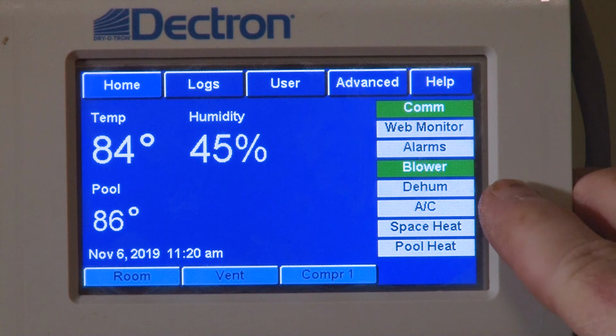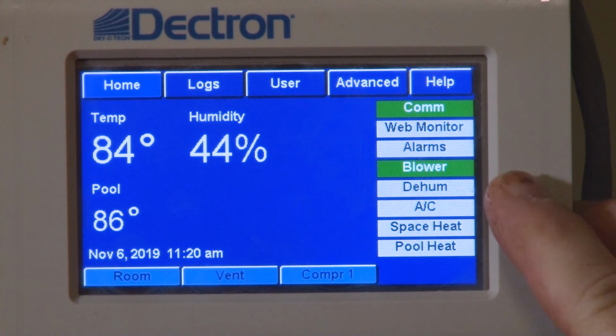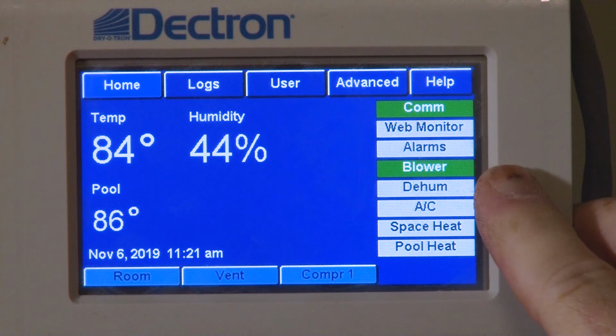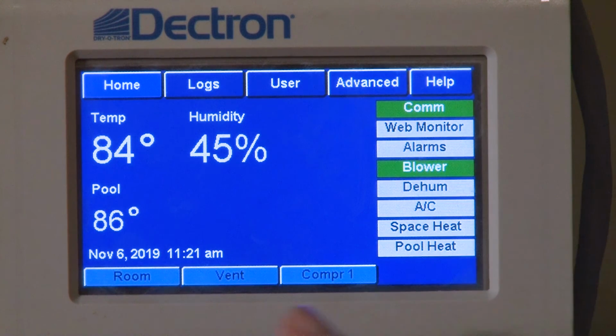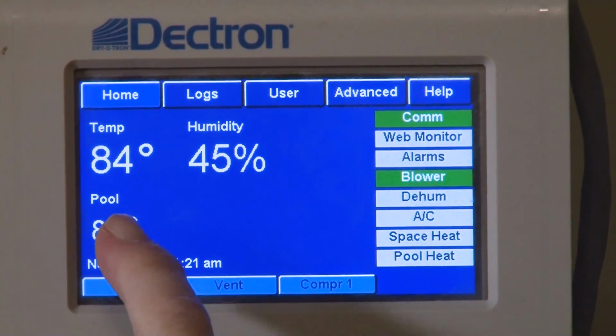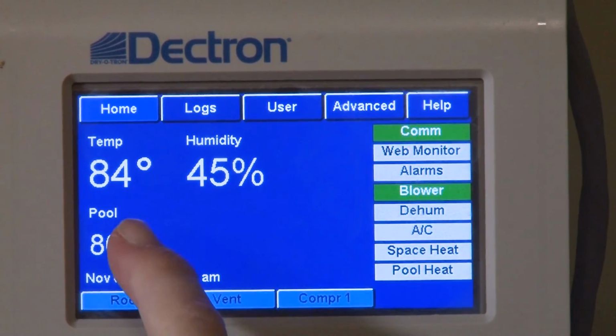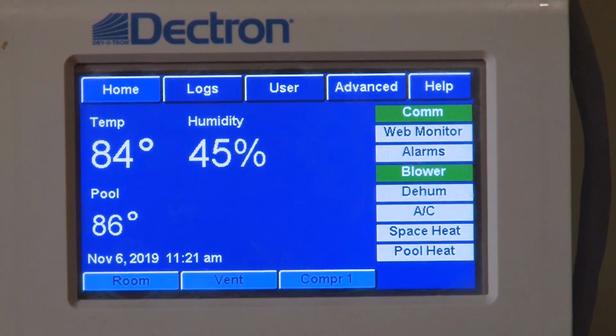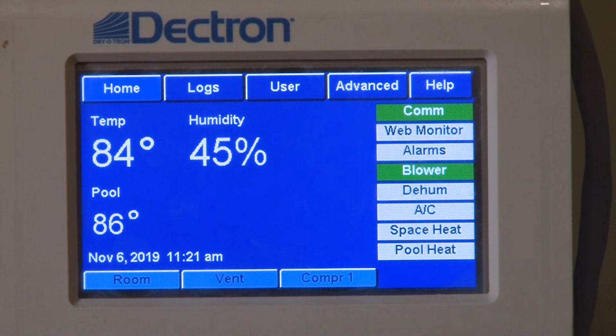So as you can see on the right-hand side of the screen, the blower status indicator has illuminated green, indicating that the blower is running. We're still measuring a room temperature of 84 degrees. I changed the set point to 88. So after 60 seconds or so, we should get our space heat status lighting up as green.